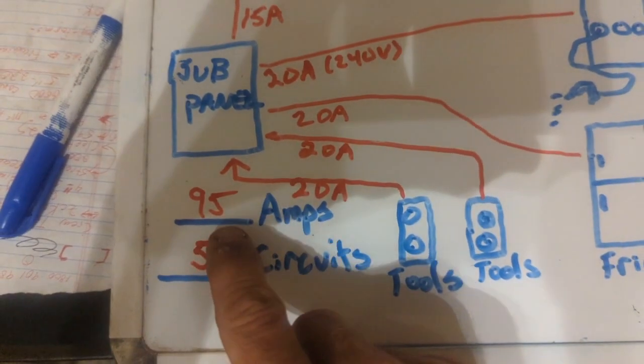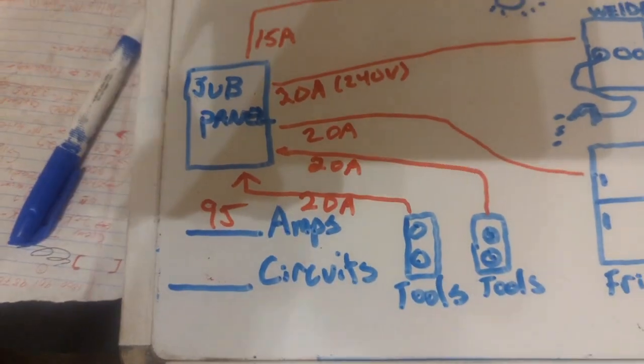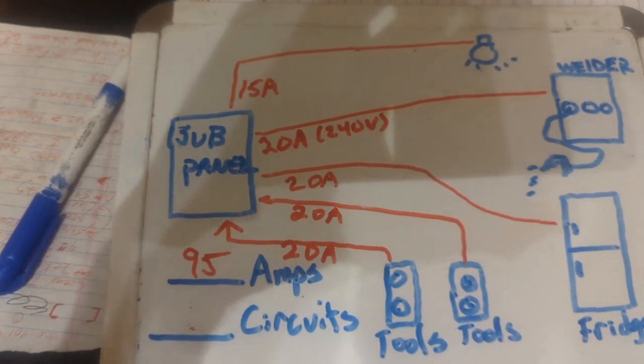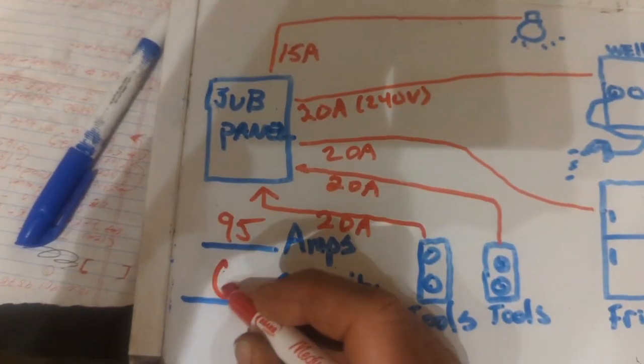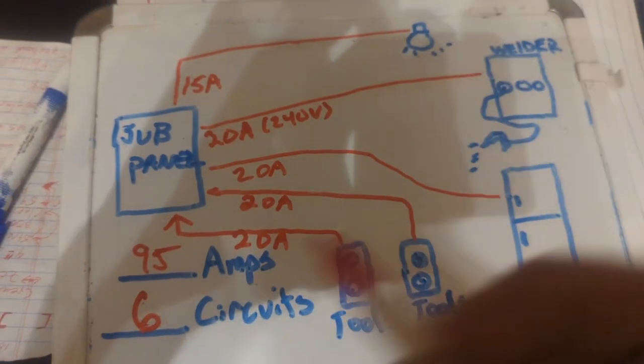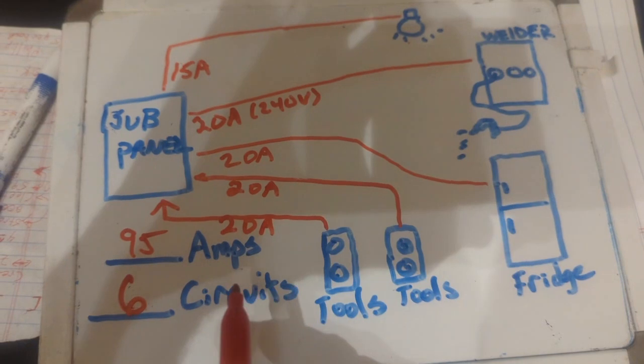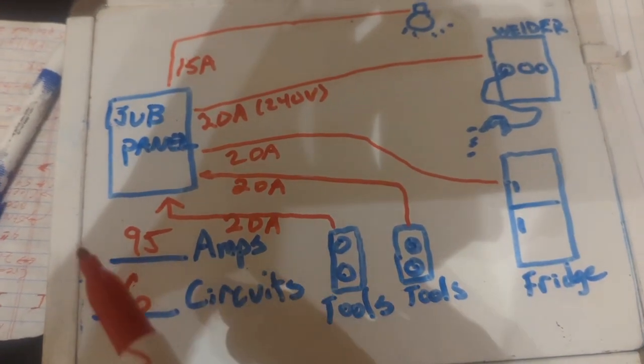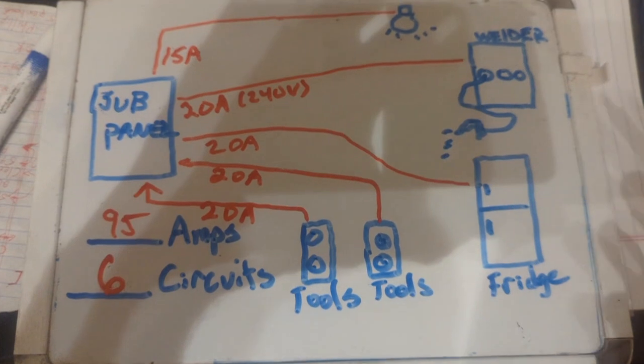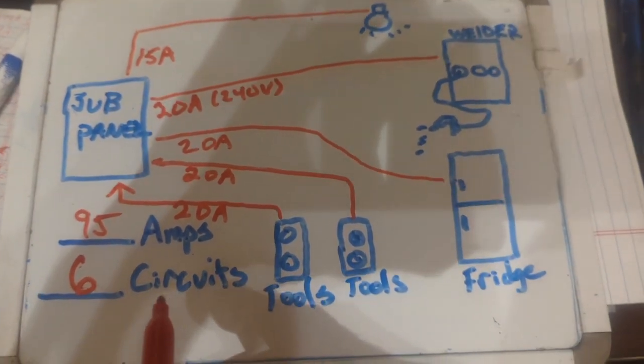So in this situation here, this is going to become a six. And so I'm going to need a sub panel with at least 95 amp capacity, and I'm going to need six slots for my breakers. So that's the bare minimum. So in some situation like this, I would be getting a hundred amp box and make sure that I have a minimum of six circuits, preferably eight because you might want a couple of spares in there.